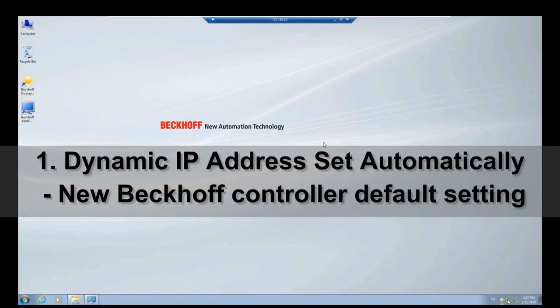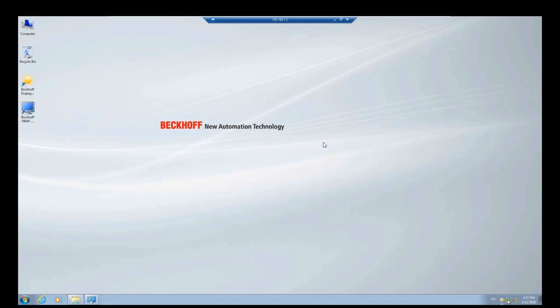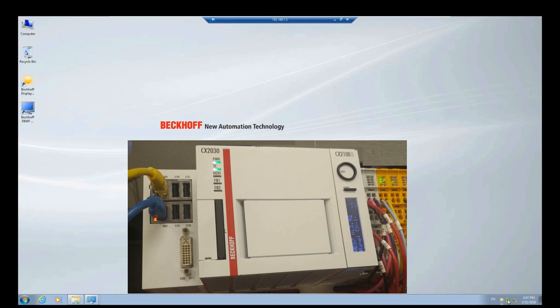The first method is for when you purchase a new CX2030 controller — by default the IP address is set to automatic inside the controller's Windows system. The second way is for when you go on-site and the controller already has a fixed IP address set. You can find this IP address from the drawings or ask your customer. In a previous video, I showed how to connect to the Windows system built into the controller using remote desktop connection, or by plugging in a DVI monitor with a USB mouse and keyboard.